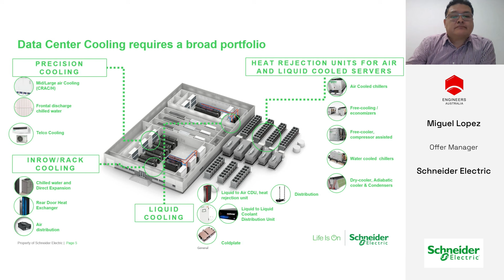So the message we want to convey today, if there's only one thing you take away from today's webinar, is that liquid cooling is not one piece of equipment, or in Schneider speak, it's not one offer. It is actually an architecture. It's an engineered system that comprises, as you can see on this slide, a technical cooling system, the TCS, supplementary air conditioning, which I just explained on the previous slide, your liquid-cooled racks, your TCS water distribution, and your heat rejection.